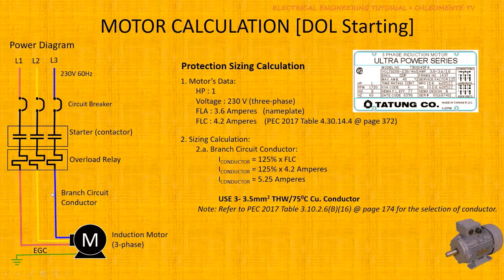First, let us size the branch circuit conductor. This is the conductor connecting your motor to your overload relay. Per PEC, the branch circuit conductor must be rated at 125% of the Full Load Current (FLC). So 125% of 4.2A equals 5.25A. Therefore, we use 3 × 3.5mm² THW 75°C conductors. There is a separate video on how to select conductors using FLC for reference.